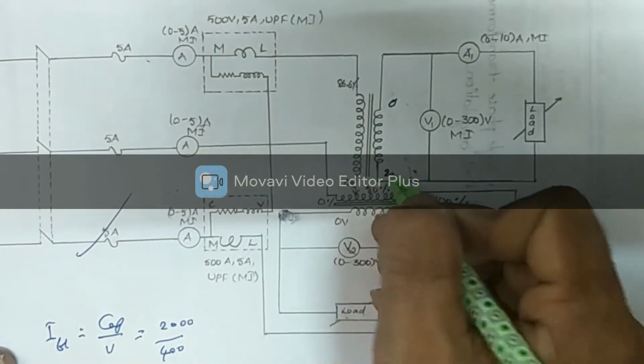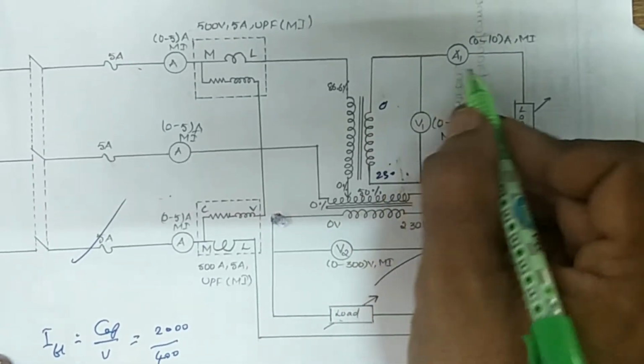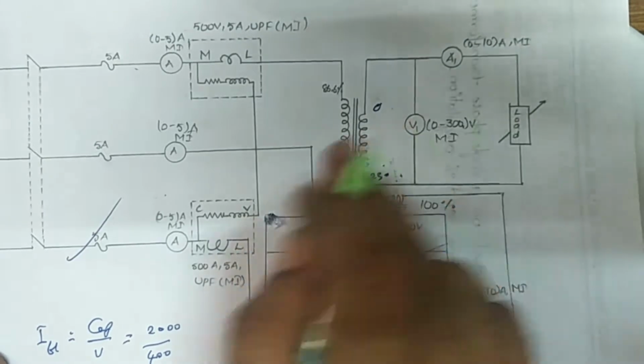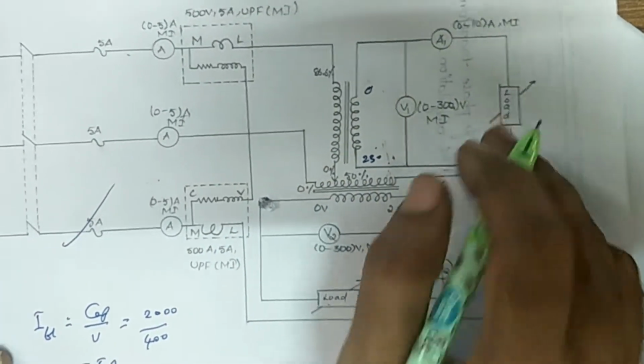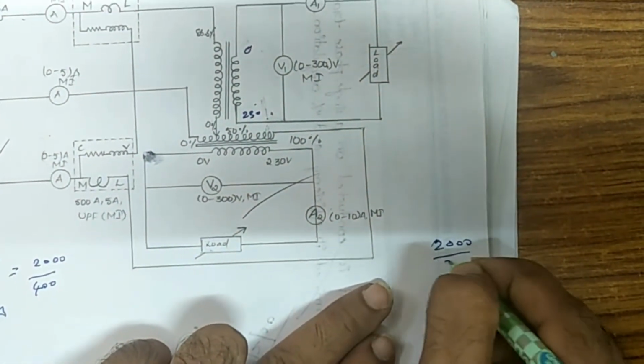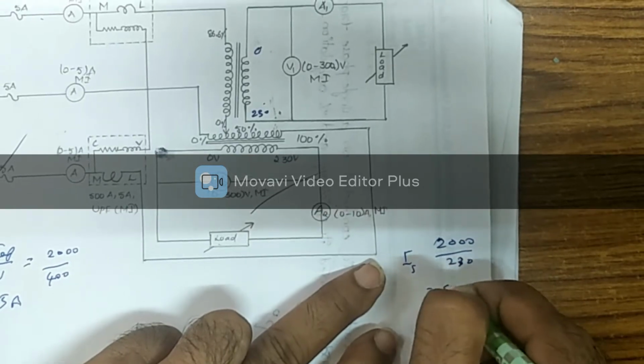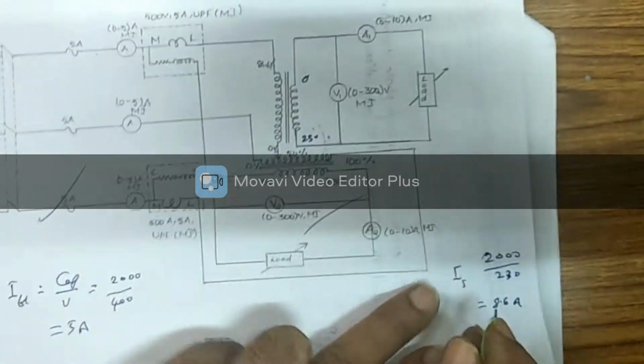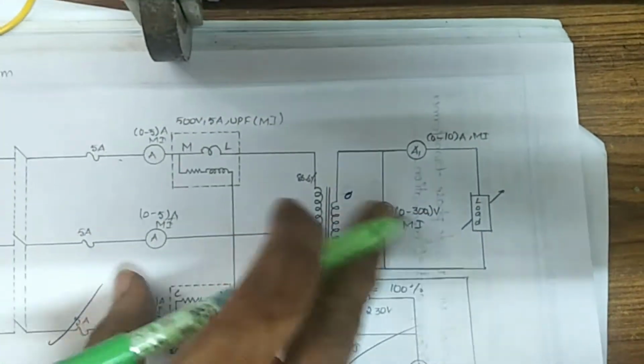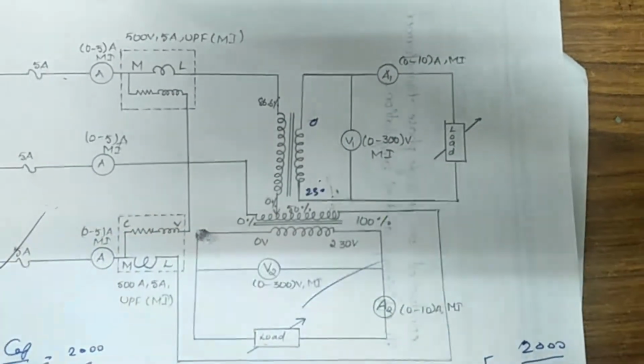Coming to the secondary side, already we know the rating of the secondary side winding is 0 to 230. Therefore the voltmeter rating will be 0 to 300. Similarly, the current rating of the secondary side is 2000 divided by 230. This is the secondary side current, which is equal to 8.6 amperes. Hence the rating of this ammeter will be 0 to 10 amperes. And of course the type of instrument used is moving iron.